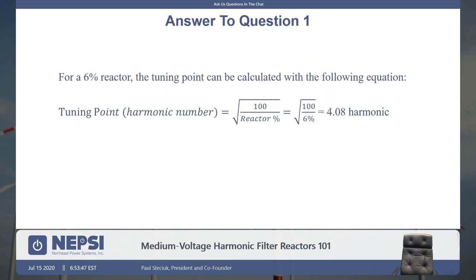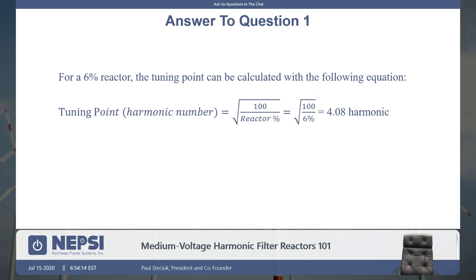For a 6% reactor, the tuning point can be calculated with the equation: tuning point equals the square root of 100 divided by the reactor percent. So the answer is the 4.08 harmonic. What does 6% mean? 6% of the capacitive reactance will equal the inductive reactance — that's what it means. Knowing the inductive reactance allows you to calculate the tuning point. It's also about equal to the voltage drop across that reactor line-to-neutral — 6% — but not exactly; remember it's N-squared over N-squared minus one.